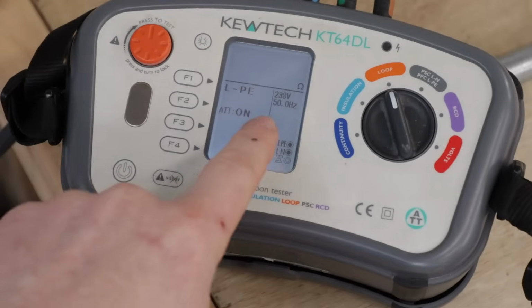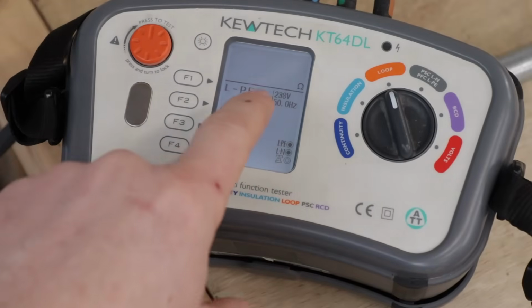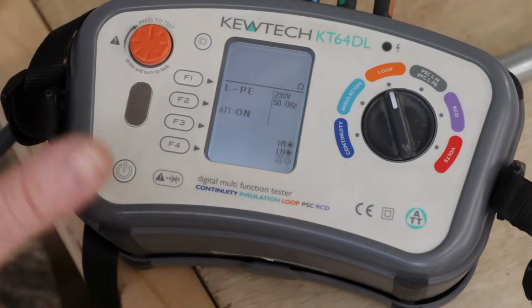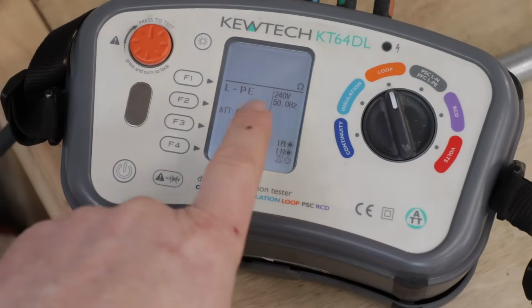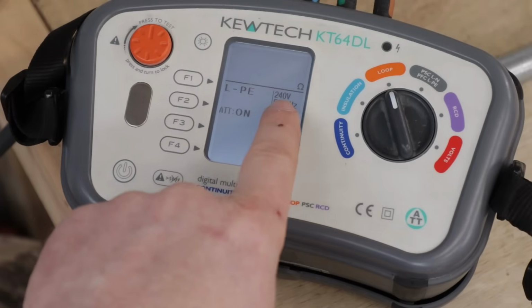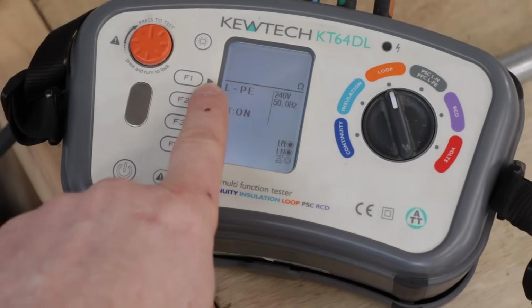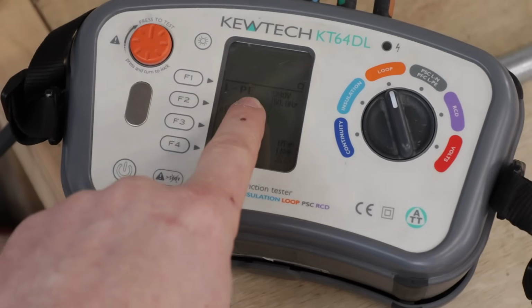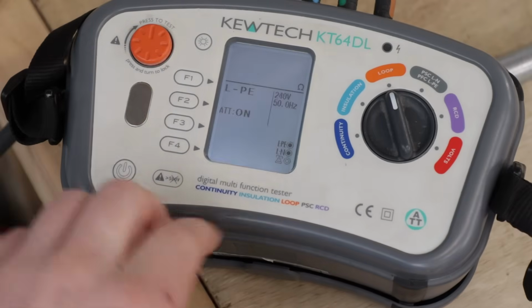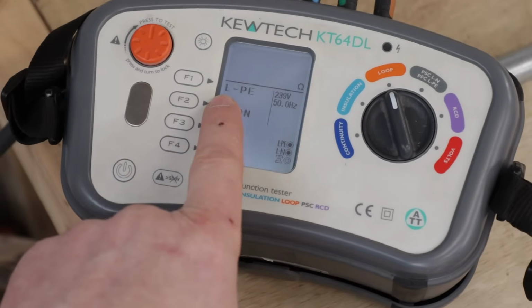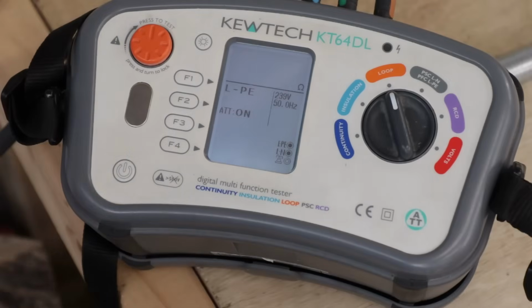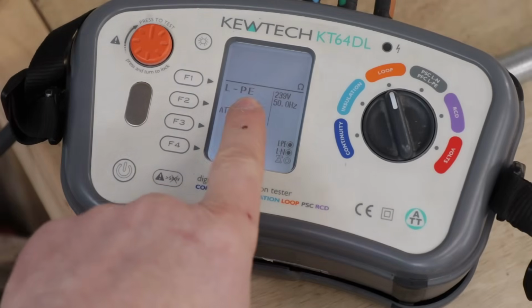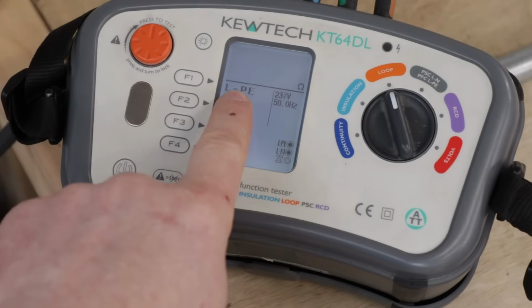Okay guys, I have my meter plugged in now. Don't worry if you don't understand this. I just want to show you a couple of figures just so this kind of hits home about the length of a circuit. So you can see I have 240 volts here, and I'm measuring my live and my protective earth. My light has gone off there now. My protective earth, like I said, is all the way through that socket, back to my board, back to my house, back out to the transformer, and back in on the earth. So that's the fault loop, it's called.